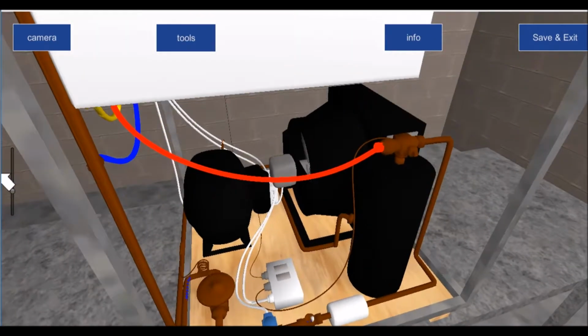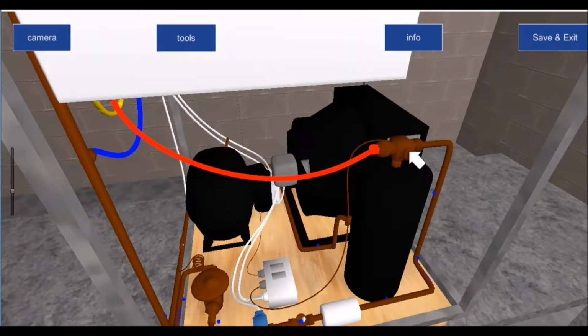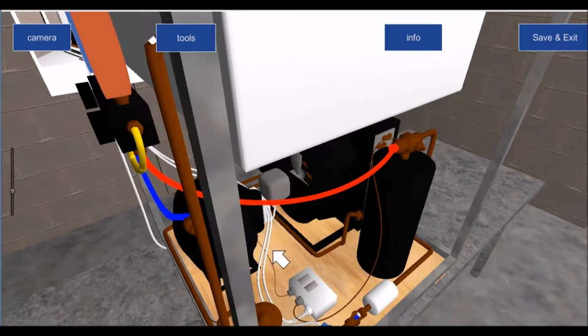And then you have another piece of terminology which is fully front seated. So if we were to fully front seat the valve all the way, and again I'll show you a valve operation in a few minutes, and I've already shown you valve operation, but I'll just remind you. If we go fully front seated, then the refrigerant will no longer be able to enter into this hose line from this liquid line pipe, but this hose line will still be exposed to refrigerant. So the only time your service port is not exposed to refrigerant is when you have the valve in the fully backseat position, okay?